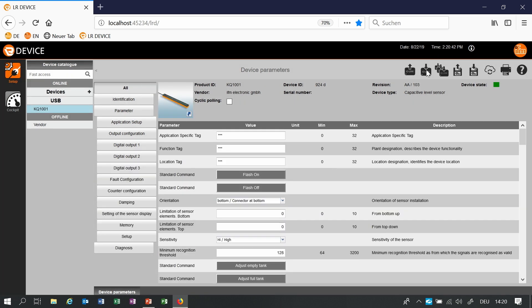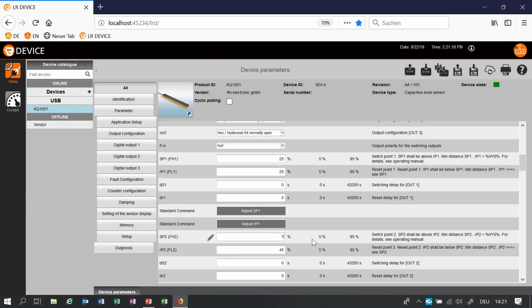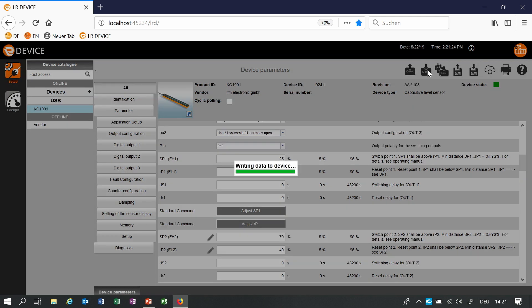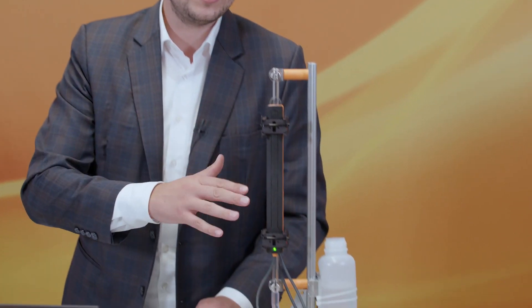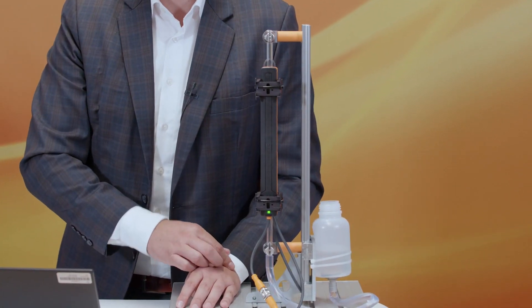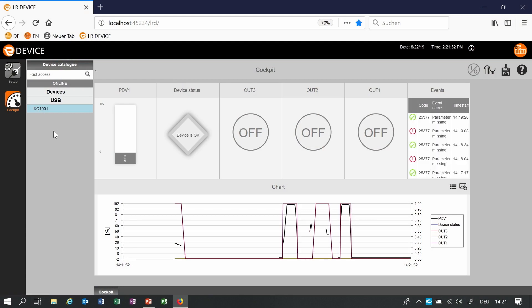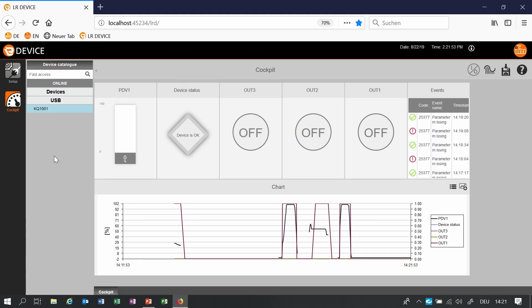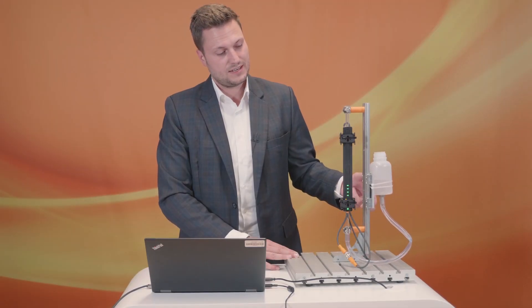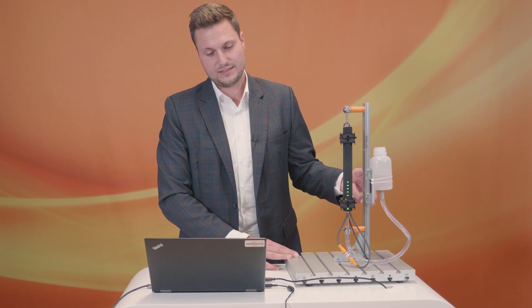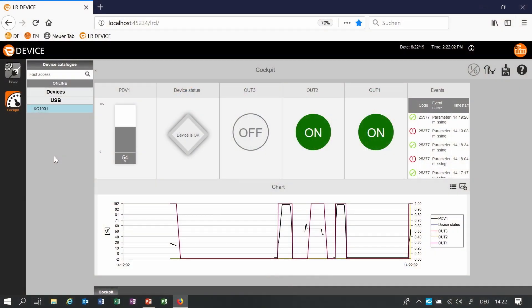For the second switch point I will choose a switch point between 70 and for example 40 and write it to the device. So it's easy to set, you just have to type in at which level the sensor switches on or off. You can use a hysteresis function which means that you have a setpoint and a reset point and we have window functions. That means that the sensor or the switch point is on in this level for example. So the second switch point should be on between 40 and 70 because it is a window function.